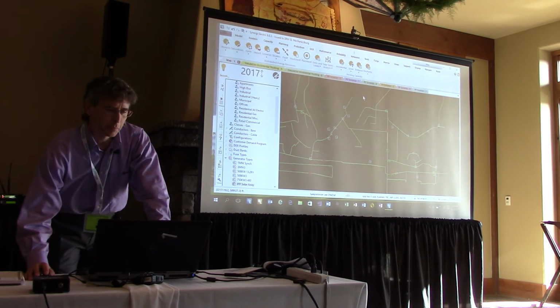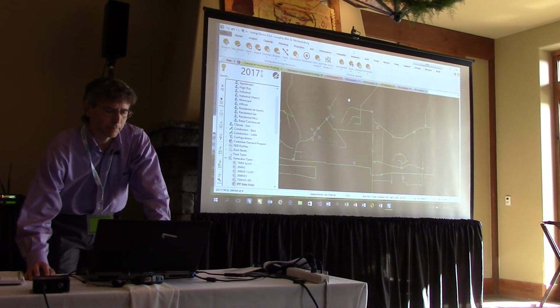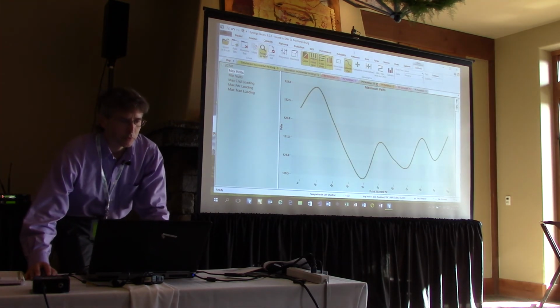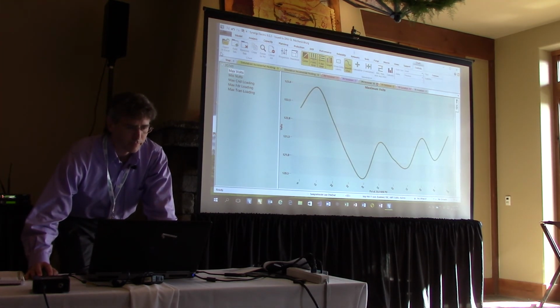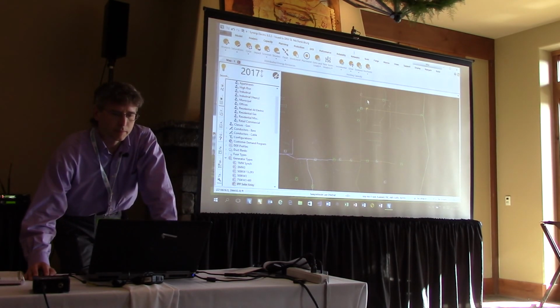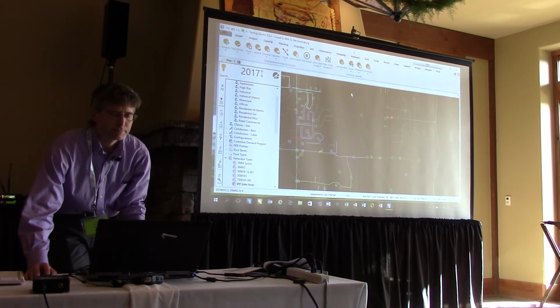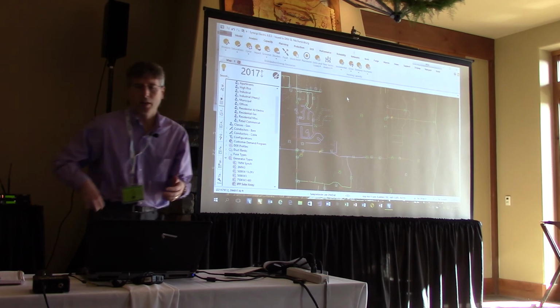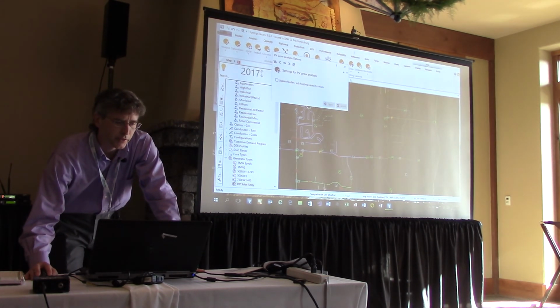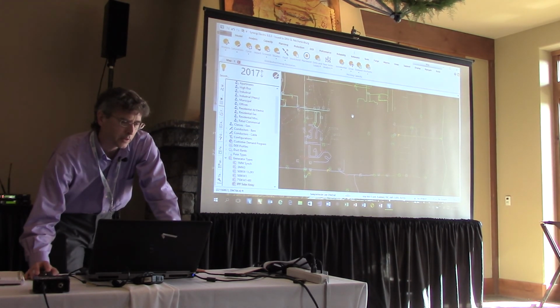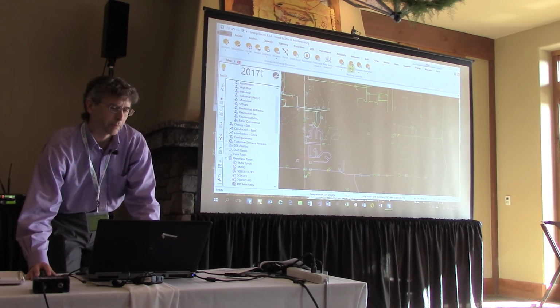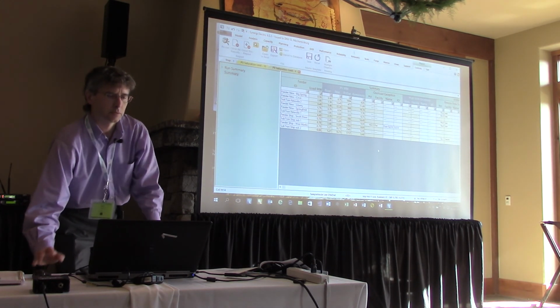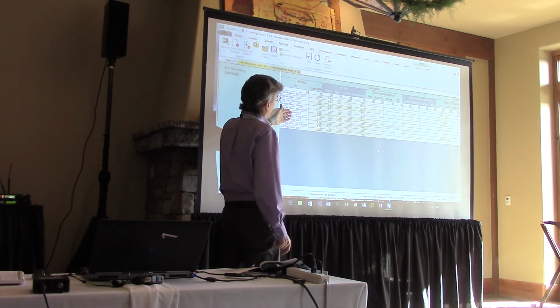So let's look at some of the other hosting capacity. One that is more about the feeder level hosting capacity is this GROW approach. And with the GROW approach, I think there's a saturation level in the setting. It's not even that. And so it's just going to start adding PV throughout the feeders until it runs into a problem. So if we run this, we get a list of all the feeders in here.